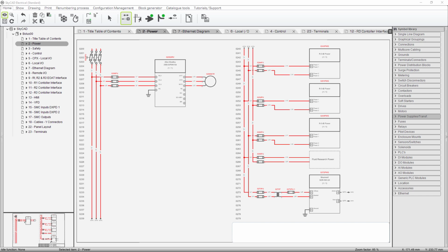Okay, so in we come with 3-phase in the upper left-hand corner. We immediately go through the fuse disconnect. You can run your 3-phase like I did in vertical strips along the line numbers. You see I have 0200 through 0239 and so forth. Or you can run them across the top horizontally and then drop your loads down from those 3 wires. I choose to put my three-phase vertical and then come off horizontally with my loads. So I've only got one three-phase load, and that's that variable frequency drive.